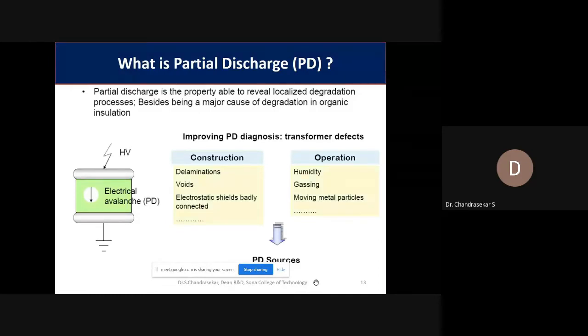If this arc continues for a long time, then it will slowly bridge, and it will short circuit the high voltage point and the ground point. Then it will lead to a complete short circuit, and only then does the sudden bursting or failure, the shutdown of the transformer, happen. Okay, so the presence of these partial discharges inside the insulation system, particularly in transformers and cables, leads to a very big failure. Therefore, monitoring these partial discharges in the initial stage itself really gives a very good preventive maintenance solution for such costly equipment.